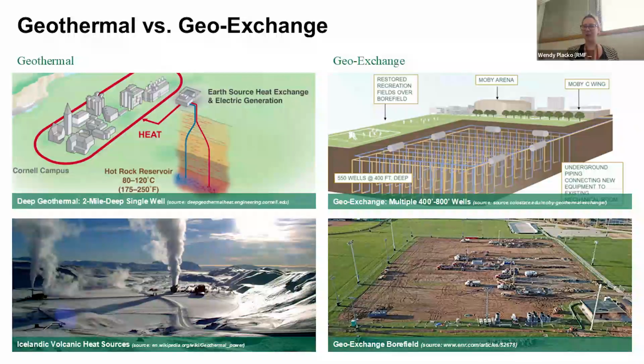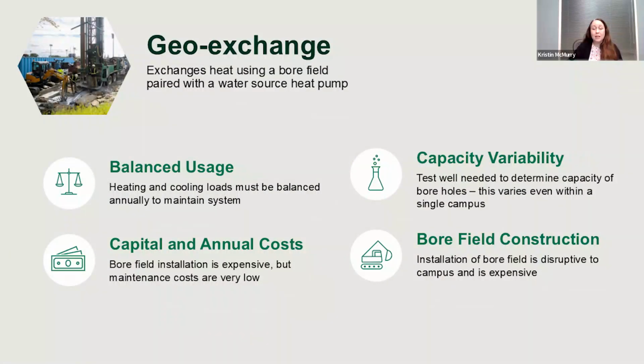Let's talk a little bit about some of the pros and cons of geo-exchange, since that's the system we tend to recommend or utilize. You're going to need to do a test well, because there's big variability, even within the same campus, for how much you can actually get from these boreholes. A rule of thumb a lot of times is 3 tons per well. So you have to do a test well to see whether it's feasible for your campus.